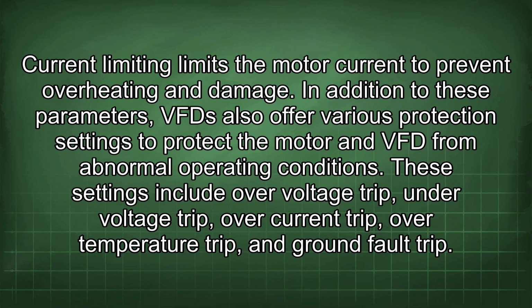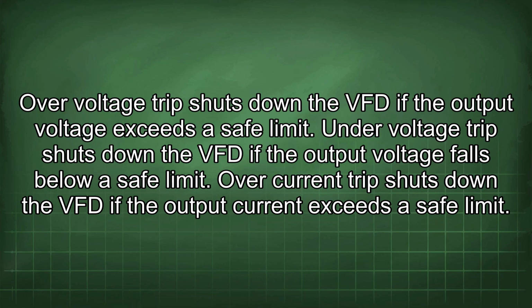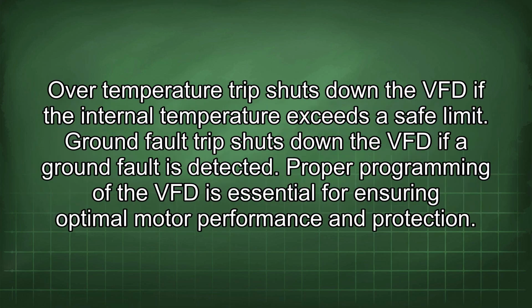In addition to these parameters, VFD also offer various protection settings to protect the motor and VFD from abnormal operating conditions. These settings include overvoltage trip, undervoltage trip, overcurrent trip, overtemperature trip, and ground fault trip. Overvoltage trip shuts down the VFD if the output voltage exceeds a safe limit. Undervoltage trip shuts down the VFD if the output voltage falls below a safe limit. Overcurrent trip shuts down the VFD if the output current exceeds a safe limit. Over-temperature trip shuts down the VFD if the internal temperature exceeds a safe limit. Ground fault trip shuts down the VFD if a ground fault is detected.